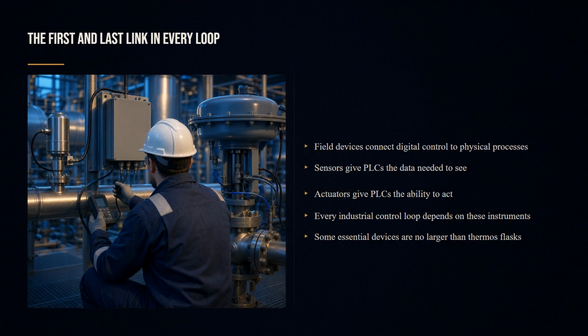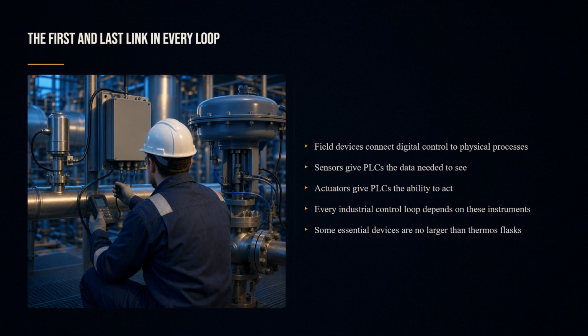Field devices are where the digital world meets the physical world. PLCs, HMIs, and SCADA serve one purpose: read sensor data and command actuators. Remove a pressure transmitter and the PLC is blind. Remove a control valve and the PLC has no way to act. These simple instruments are the foundation of every control loop in every industrial facility on the planet. Some are no larger than a thermos flask.